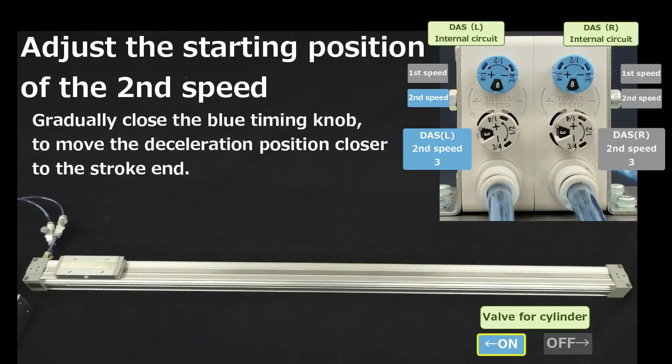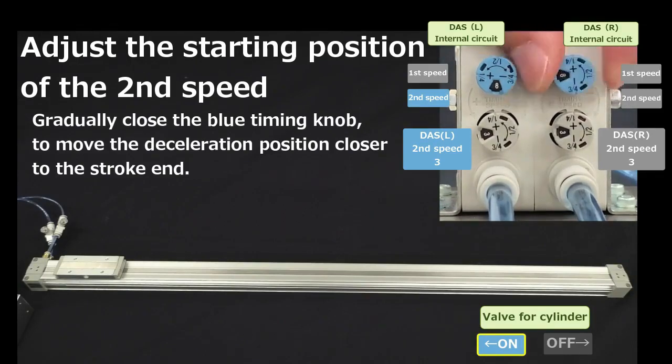Next, adjust the deceleration position. Gradually close the blue timing knob to move the deceleration position closer to the stroke end. Make adjustments to fix the desired deceleration position.